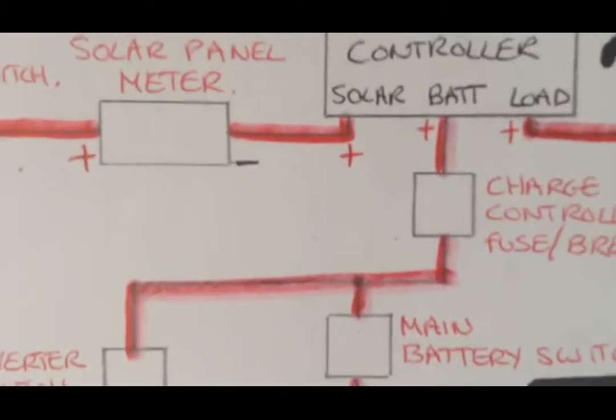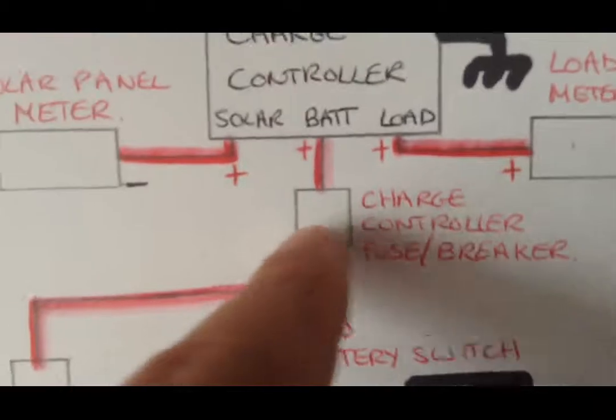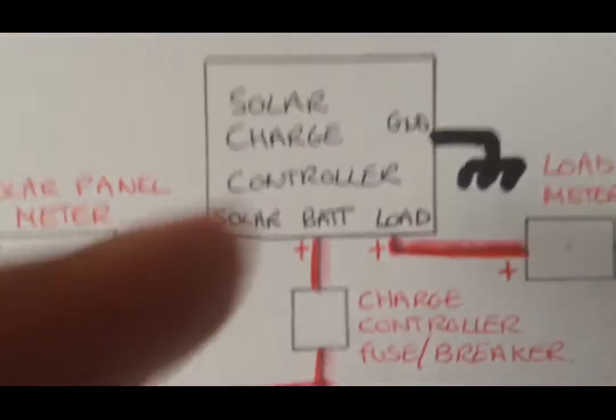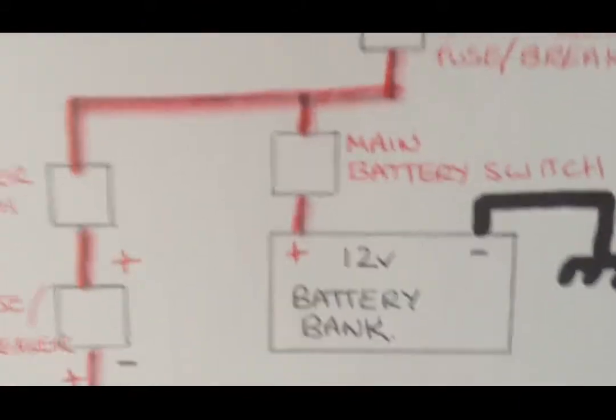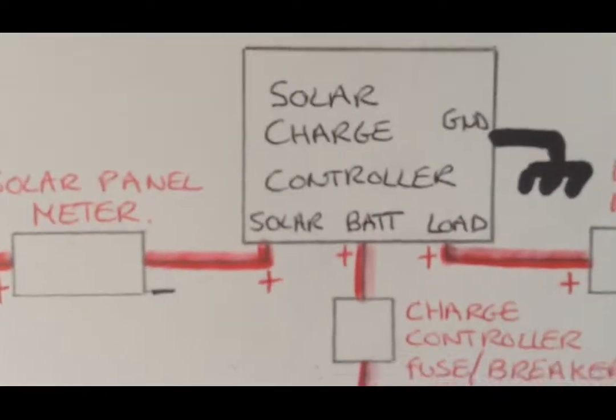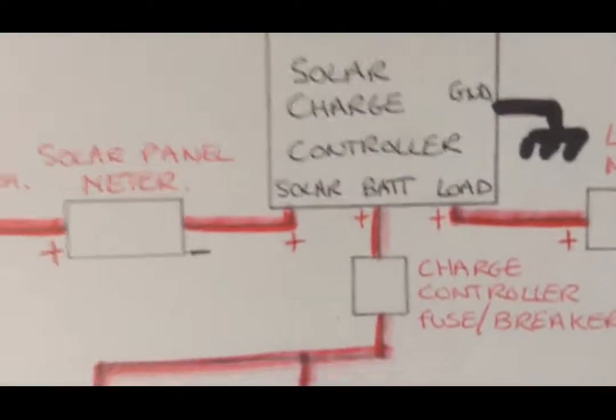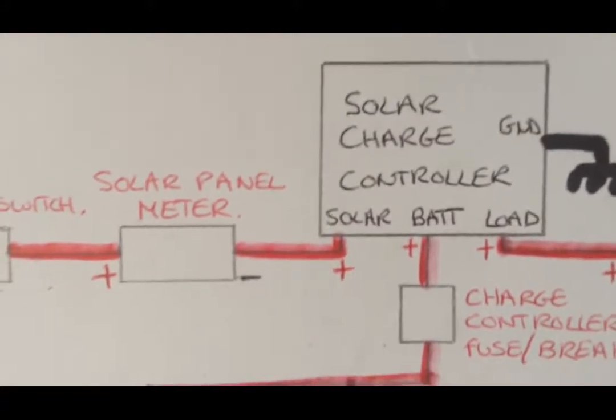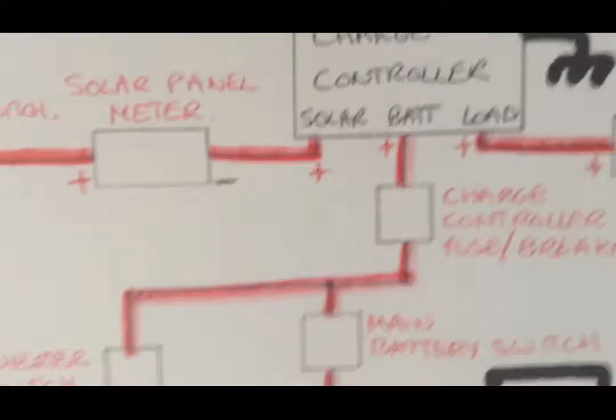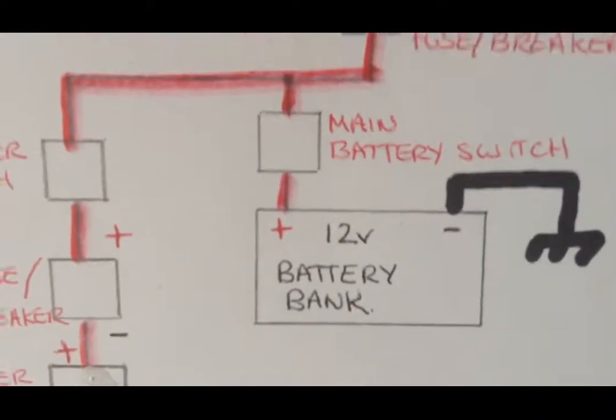That's the way it works in this case, because this fuse or breaker is here to protect the solar charge controller. If it goes wrong internally and shorts the battery input together, as an example, the plus and the minus get shorted inside the charge controller, then your battery will try to push as much current as it could into the charge controller, which is very bad. This will get hot, smoke, and may even catch fire. And your wires might too, and the battery might overheat as well. So to prevent that, you need to use a fuse or a circuit breaker.